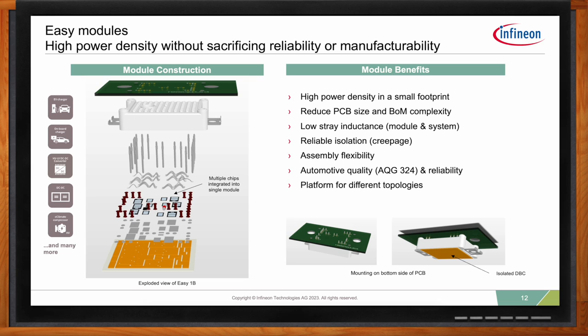Not only do you have very symmetrical chips, but you also reduce stray inductance. The chips are soldered onto the back of the DBC substrate so heat is evenly spread. The DBC, or direct bonded copper substrate, is a ceramic material that is fully isolated and has very high thermal conductivity, resulting in very low thermal resistance from junction to case. Because the DBC is isolated, there's no need for any isolation foils or the risk of them moving out of place and exposing a live surface. Additionally, built-in mounting clamps for the heat sink keep the module in place and maintain compression of the standard gap pad or gap filler without any additional components. Inside the package is filled with dielectric gel for a fully isolated module.